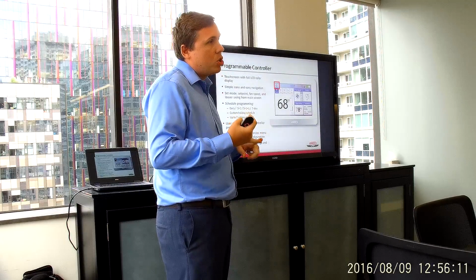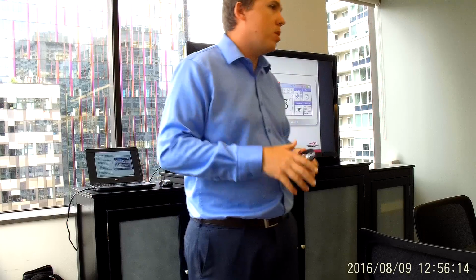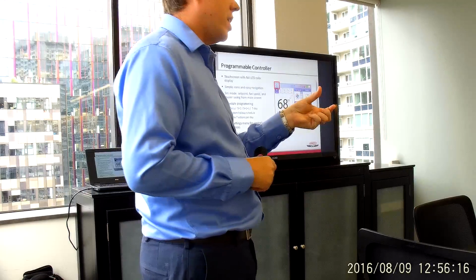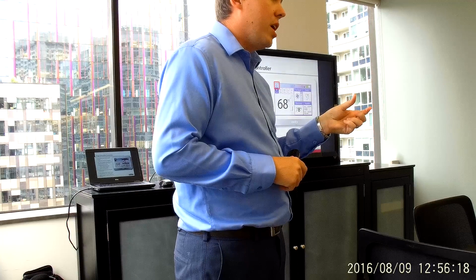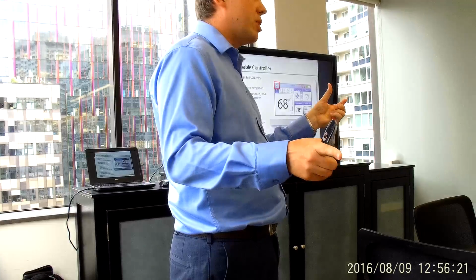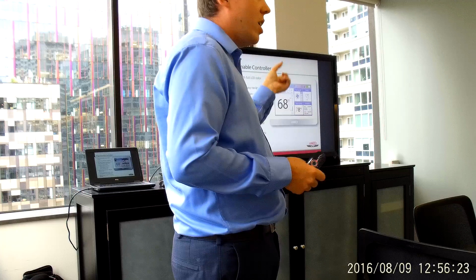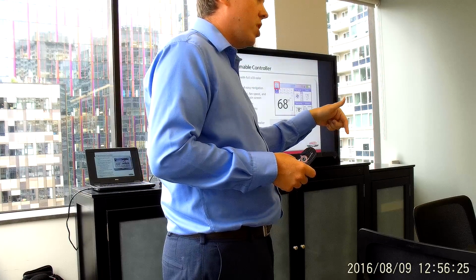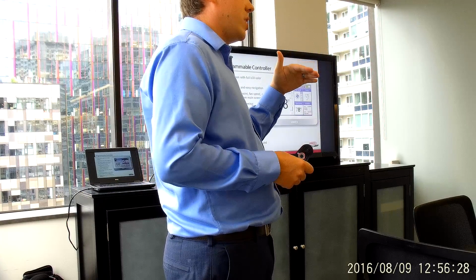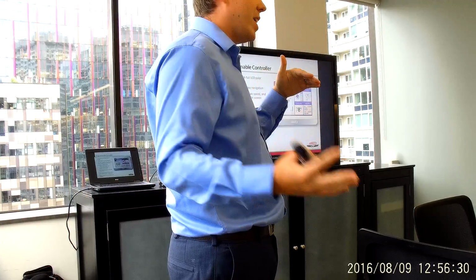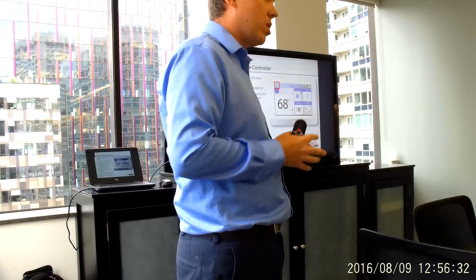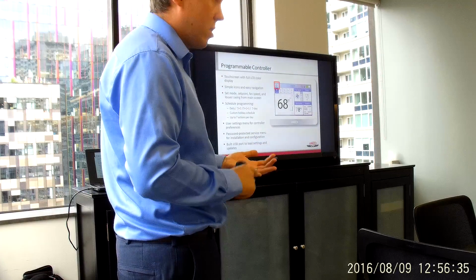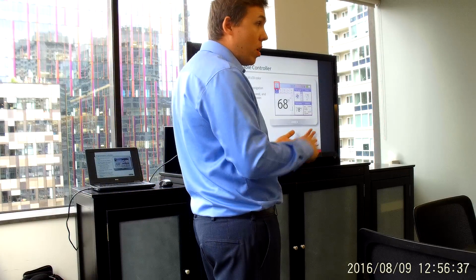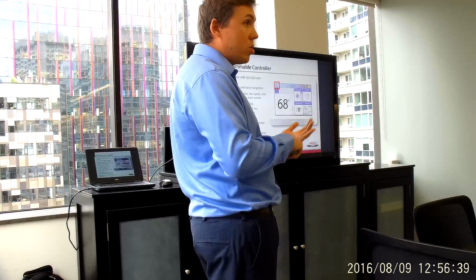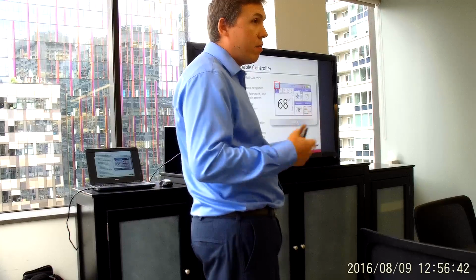And what that allows them to do is, if the ambient condition drops below a certain temperature, it overrides the indoor operating mode of the fan coil unit and switches it automatically on that baseboard heater. It's a setting we can adjust on there. You can also control on indoor room temperature. If that room temperature starts to drop below that set point and the unit can't keep up, it'll bring that in as an auxiliary heat with the unit. You can set what that unit does. Do you want the indoor unit to run in fan mode while the duct heater is operational? Do you want it to switch off if it's a baseboard and not have that fan movement? You just want it to switch into fan mode, as I mentioned.